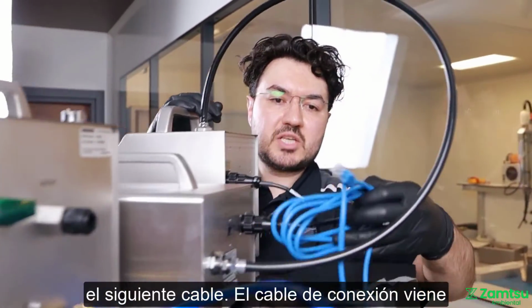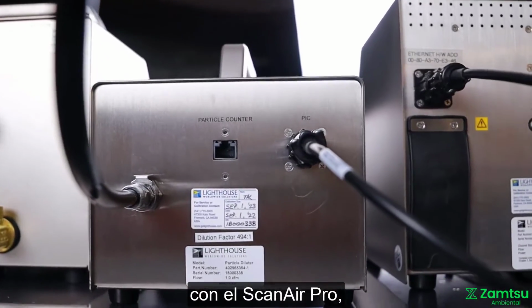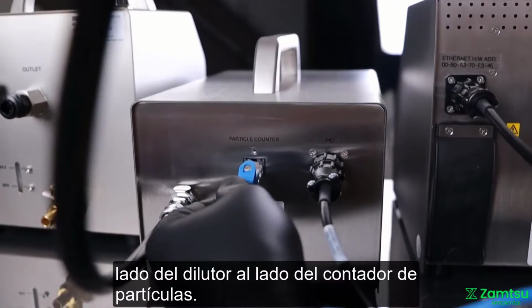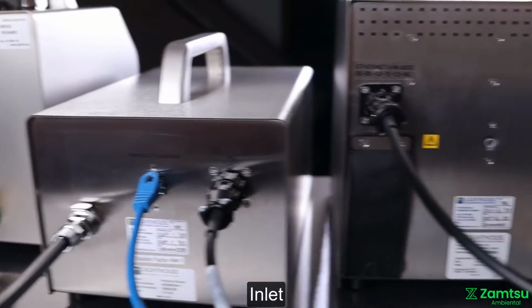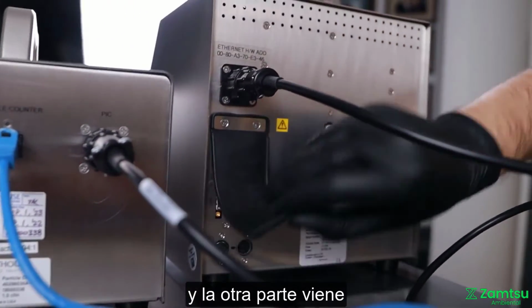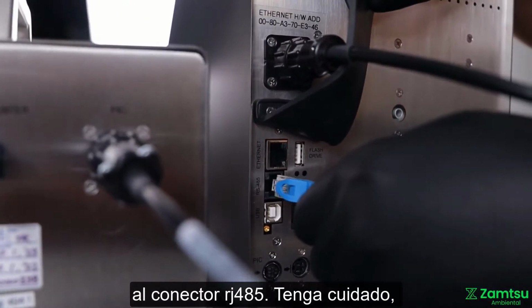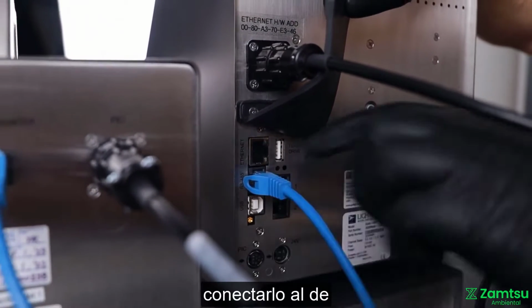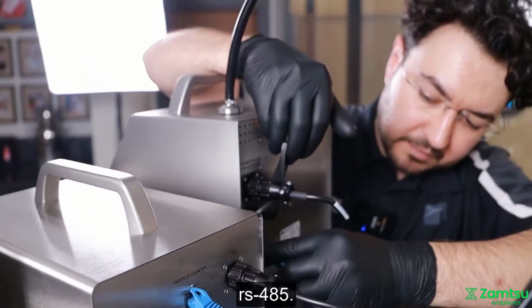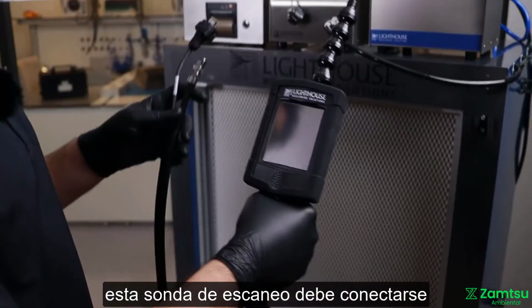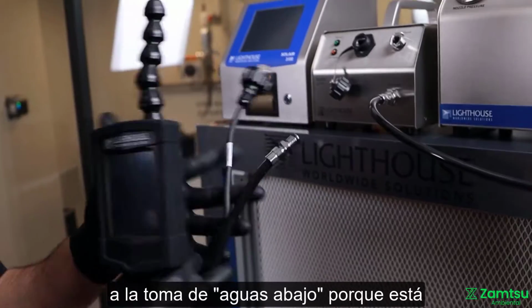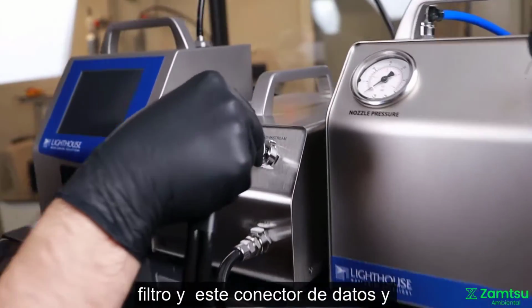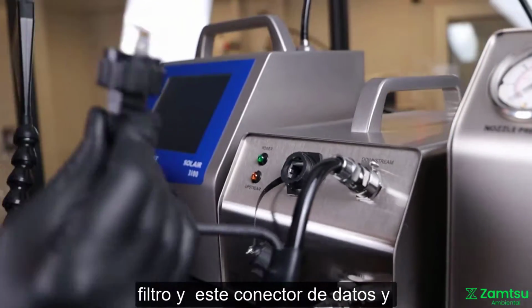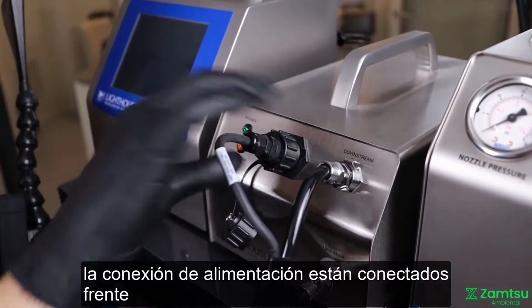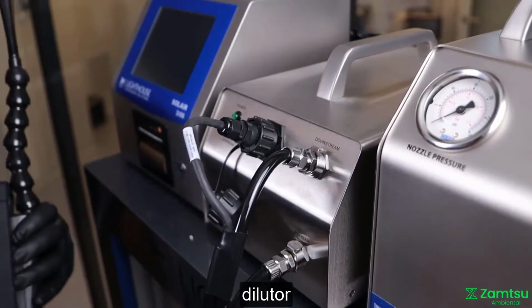The next cable is the patch cable, which comes with the Scanner Pro. It has to be connected to the diluter side, to the particle counter inlet, and the other part comes to the RS485 connector. Be careful, you shouldn't connect it to the Ethernet, but it will be connected to RS485. Now, this scanning probe has to be connected into the downstream because you are scanning the downstream side of your filter, and this data connector and the power connection is connected in front of the scanner diluter.